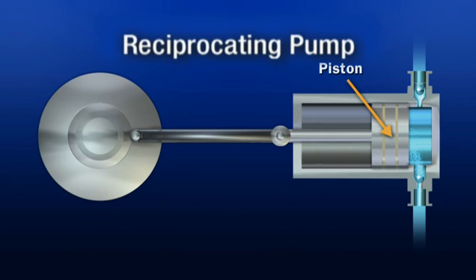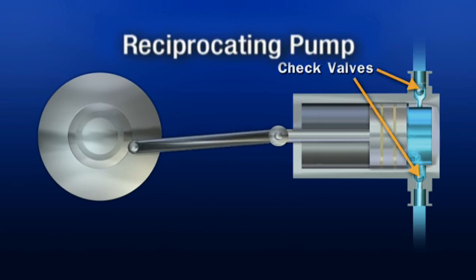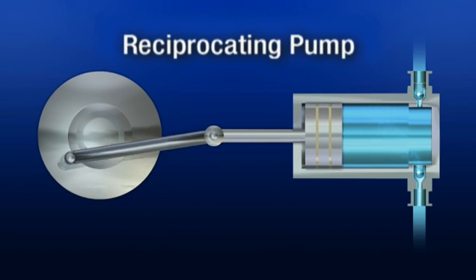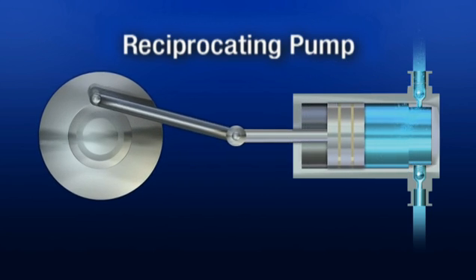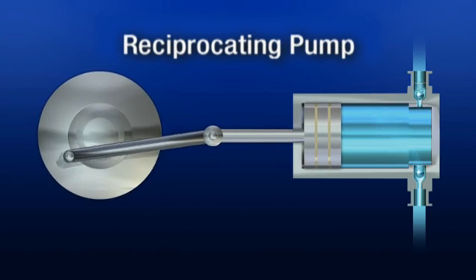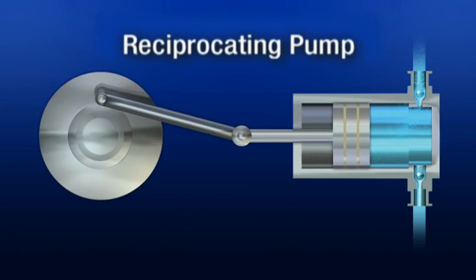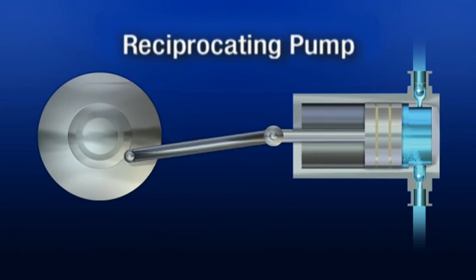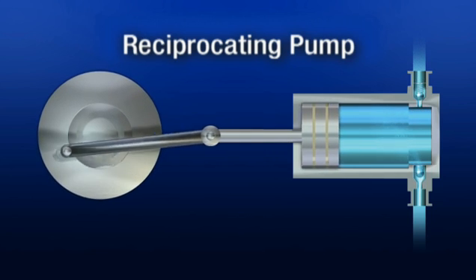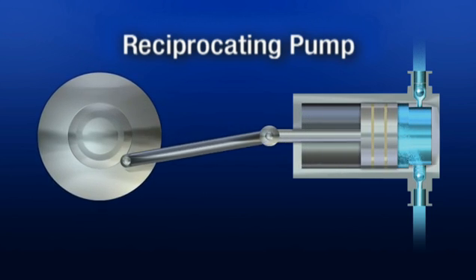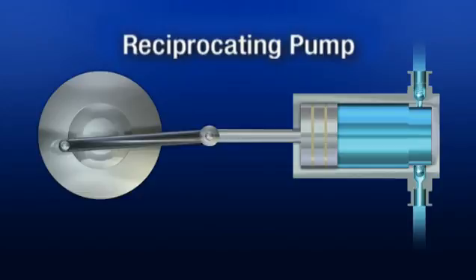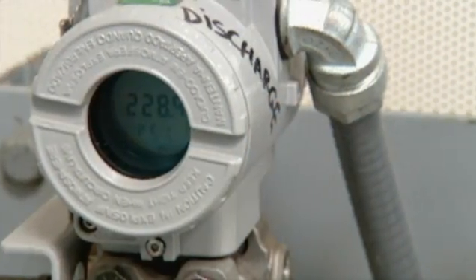Reciprocating pumps have a piston that moves back and forth in the cylinder. Liquid is admitted and discharged through a check valve. These pumps are used with very high pressure applications and where abrasive or potentially hazardous liquids must be pumped. Pumps that feed chemicals for water treatment are a prime example.